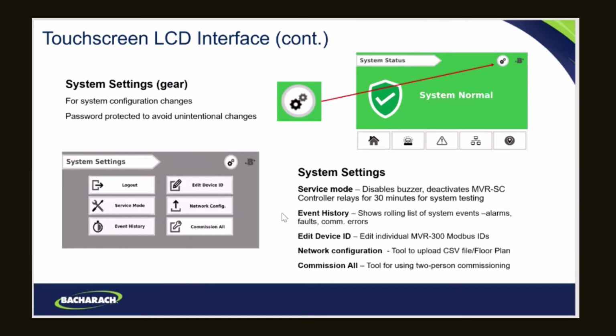There's an event history that just shows a rolling list of events that go on with the controller. It'll keep track of all the faults and the COM errors and things like that. There's a real-time clock in this that will need setting at commissioning, and that's how it keeps the event history. There is edit device ID. This is how you edit the individual Modbus IDs on each one of the gas detectors that are connected to it.